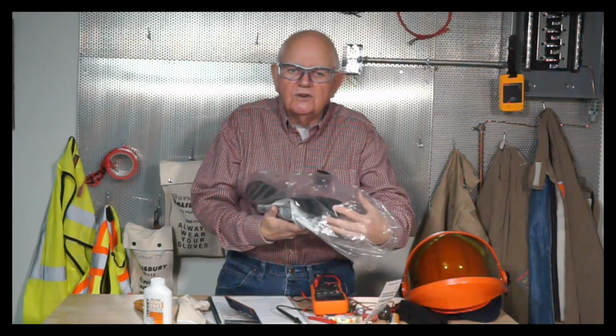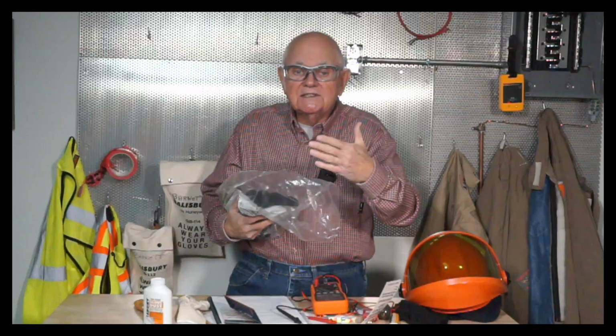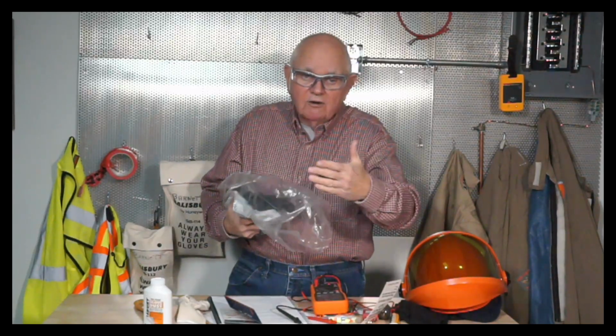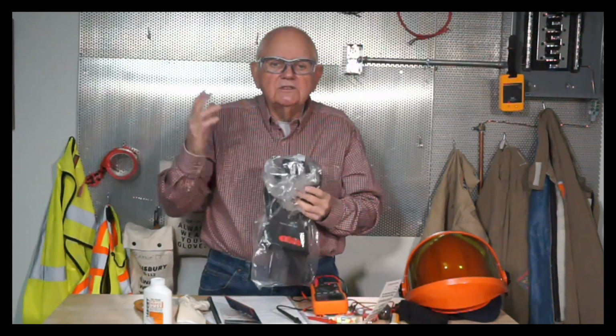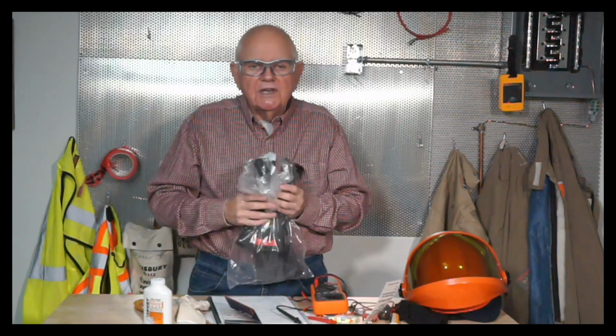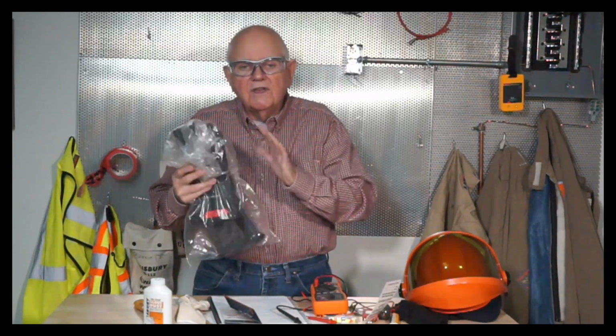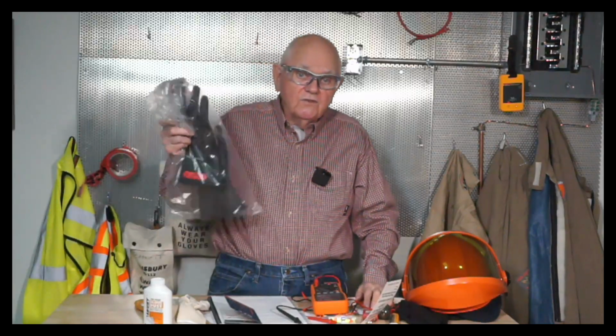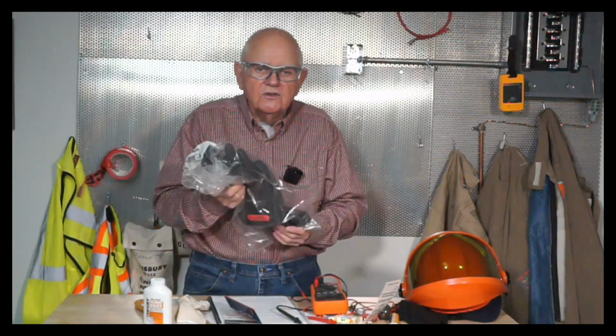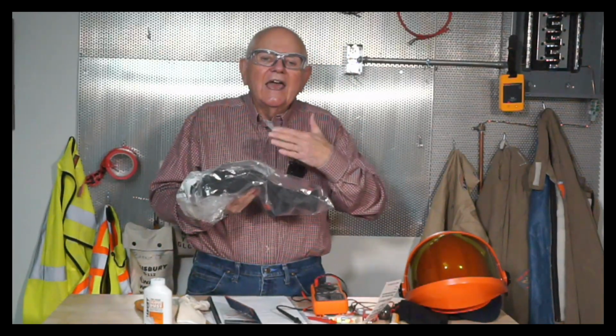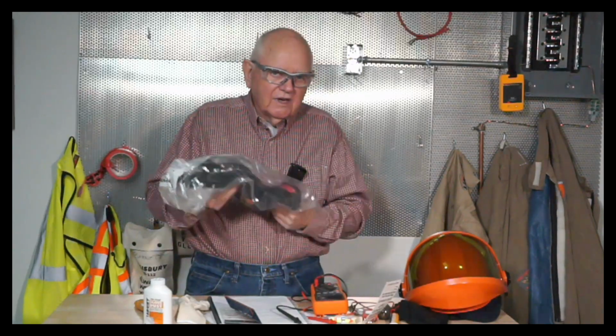They are now issued for use, and then they have to be retested 6 months later. So that would be the end of June. So I test them January 1st, and then issue them at the end of December. That's fine. And then I test them 6 months later, the end of June. Now I bring them in and get them tested, and they have been issued for use once, right? So now they have to be retested every 6 months thereafter. So I don't get that 1 year grace period up on the shelf anymore. I have to test them every 6 months.